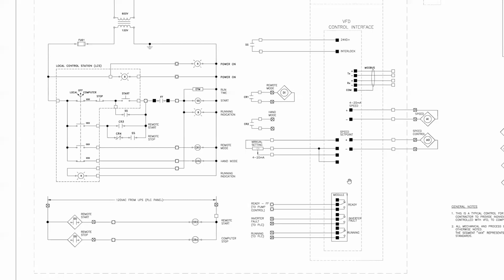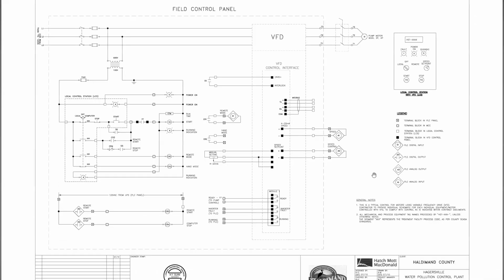So this is a pretty good example of a generic, typical drawing you'll find in an engineering drawing set. Sometimes this is the best you get, even for as-built drawing sets, as to how things would be wired. Note, there are no wire numbers on this. There's a conceptual layout of how things will work, but you are so devoid of information from this drive, because this doesn't even know what make and model of drive you have yet, because that hasn't even been specified.